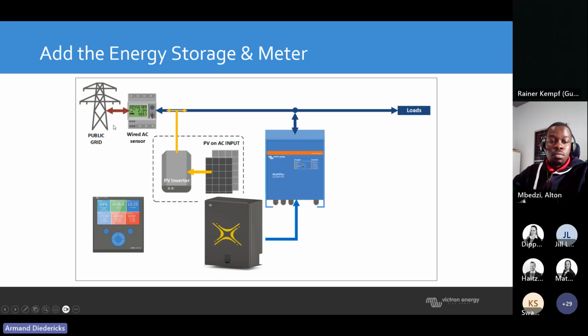The only disadvantage on this ESS or AC coupled system is your PV inverter will switch off once Eskom switches off. If your power utility or your power grid switches off, a grid tie is voltage reference based. So if it doesn't get the voltage reference on the grid tie system, it will switch off. So it's actually a big disadvantage because you won't use the sun. If you've got load shedding during daytime, your modules won't produce power, and your return on investment calculation will be poor.